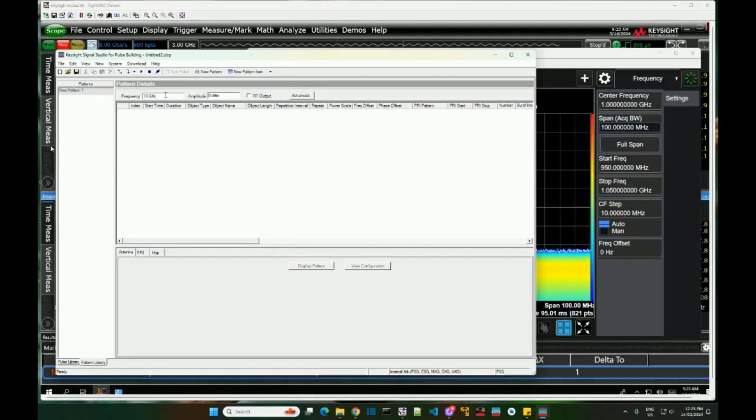And because my connections is using BNC cable, so there's a frequency limit to 1 gig. I will change that to 1 gig. Oh, sorry. Before we change anything here, we have to make sure that we have a physical connections to the PSG. So how do we connect this software to the PSG? The only information that you need is the IP address of the PSG, whether you connect dynamically using DHCP switches or static. It's up to you. As long as you are able to connect to a PC or computer that runs this software, then we click on this icon, connect to instrument.